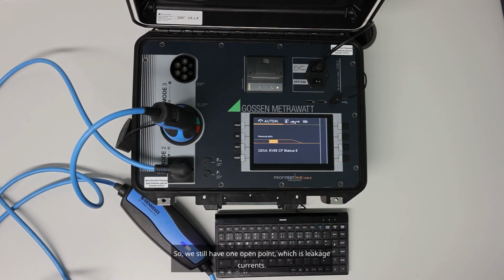So we still have one open point, which is leakage currents. Leakage currents can also occur. And that is what we do here. We check the residual currents. We can do that. We have a small internal coil. No problem at all. It is important that these are below the limit value. So those will then also be documented.